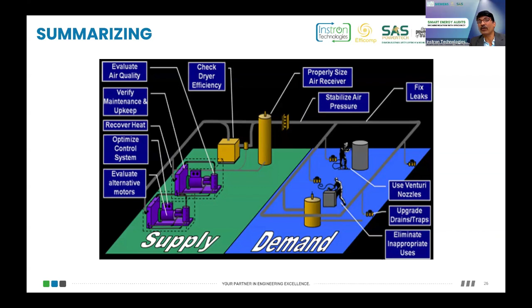Here are a few examples, case studies, which can be seen here. This is a live example where we did this in a pharma industry, where they use hot water for their HVAC system for maintaining a precise temperature at the production area. Generally they had a steam heater which was heating that water to around 40 to 45 degrees centigrade. We identified this and installed a heat recovery unit on the compressor, which generally runs 24/7, or 350 to 365 days in a year.